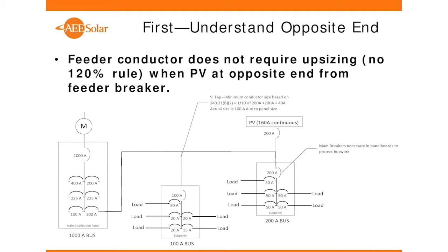Okay, so let's look at this, understanding the opposite end. If our PV system's way over here, then we don't have to upsize this conductor at all because it's already sized for 200 amps. Our inverter is actually only putting out 160 amps, so we size it up from there. It may be coming out of a 200 amp overcurrent device, and we're good to go. Now, this panel over here may have been a main lug only panel because the feeder breaker covered the loads in that panel and would protect the panel normally. So if this happened to be a main lug only panel, then we would have to install a 200 amp breaker in here. And why is that?